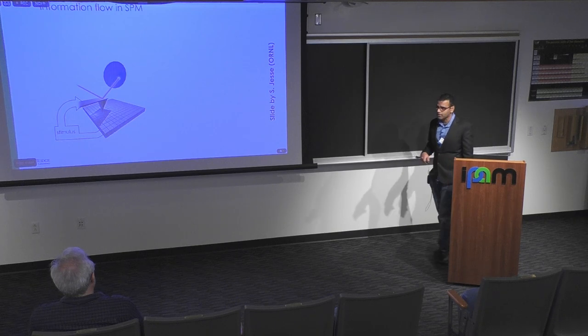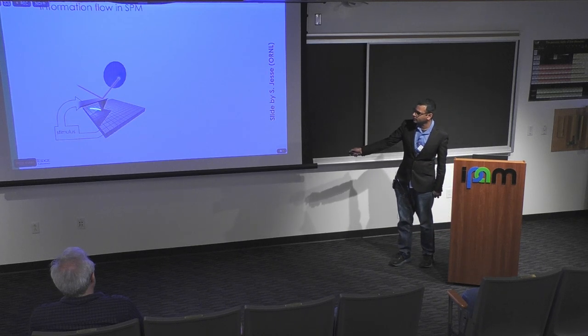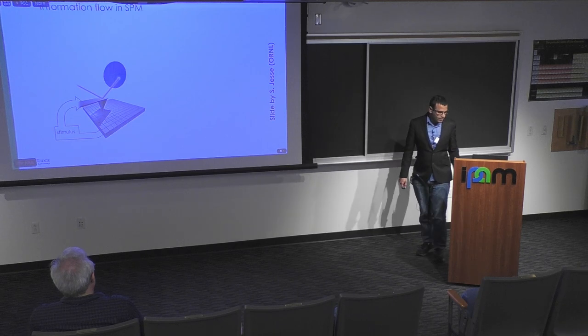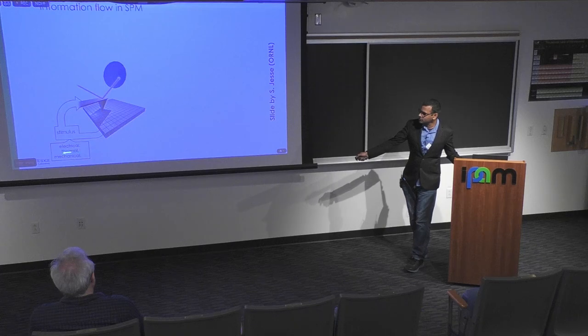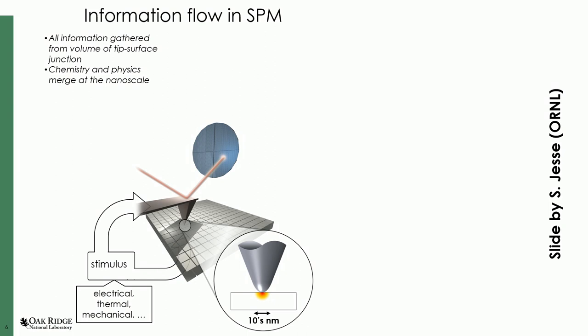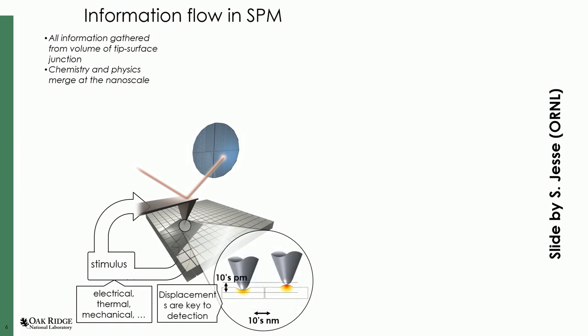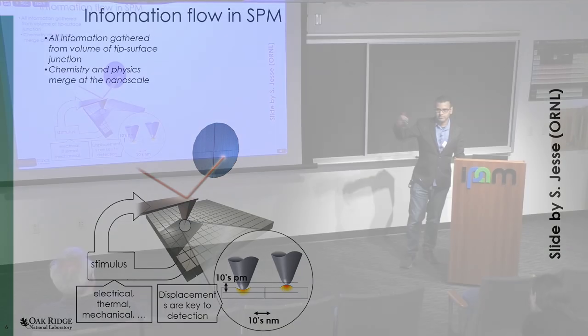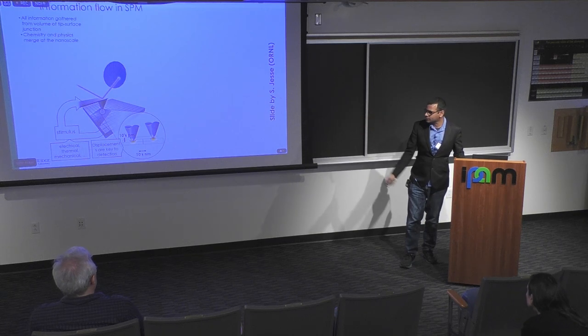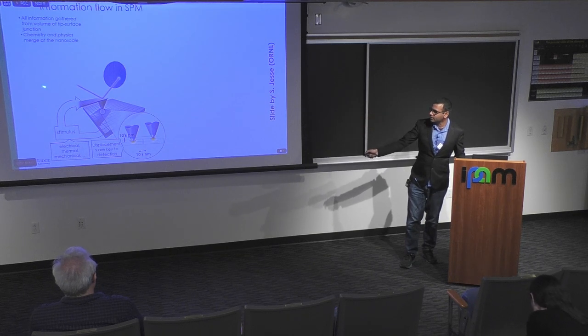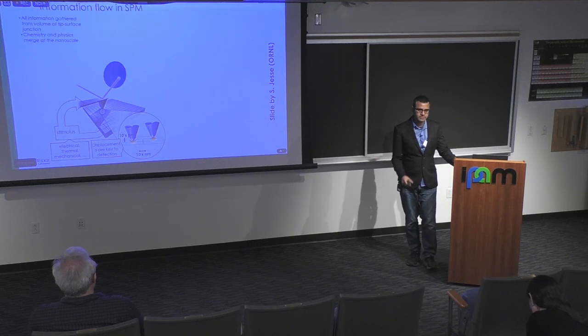We can extend this by applying different types of stimuli, for example mechanical or electrical stimulus to the probe or the sample, which can be electrical, thermal, or mechanical. This technique gives us very nice lateral resolution on the order of the probe size, around 10 nanometers. But interestingly, it also gives very sensitive measurements in the Z direction, letting us measure displacements on the order of 1 to 2 picometers. For reference, the diameter of a hydrogen atom is about 180 picometers, so these are very small displacements reliably tracked through atomic force microscopy, hence the name.